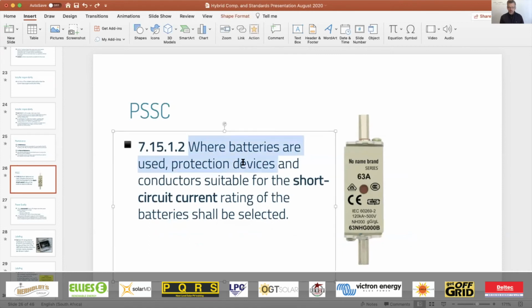Where batteries are used, protection devices and conductors should be suitable for the short circuit current rating. This is interesting. So over here, of course, we are talking about that kA rating. On the fuse in the image, we've got a 120 kA rating. And yes, this is where you see the 500 volts, and you can see the sine wave.